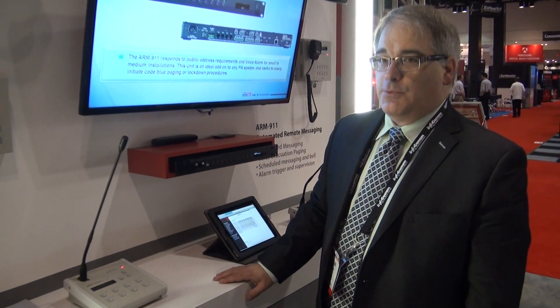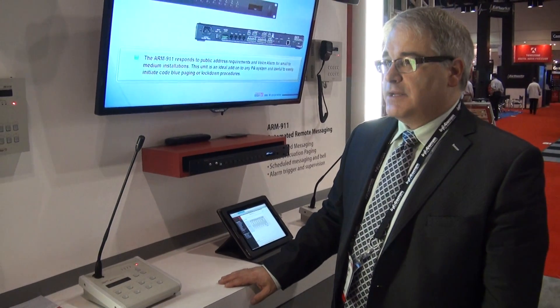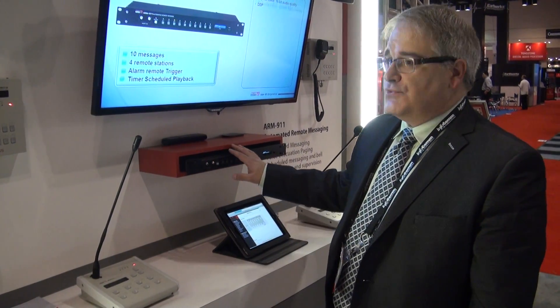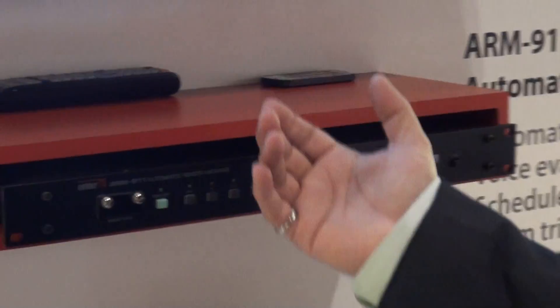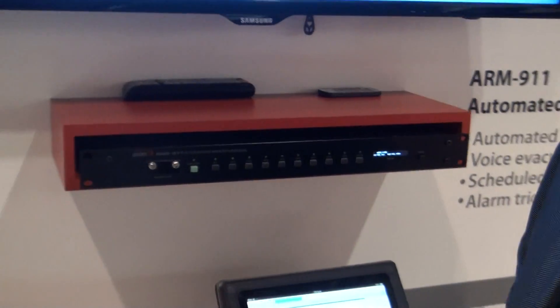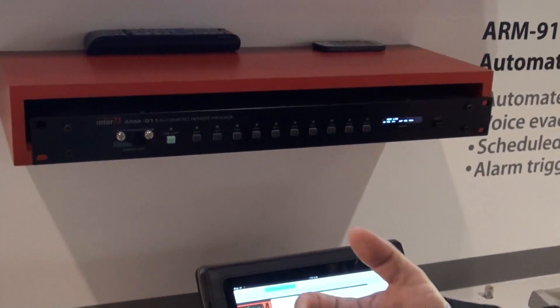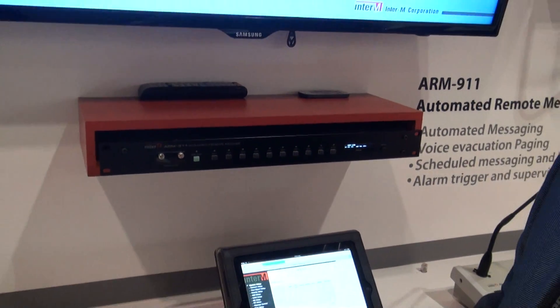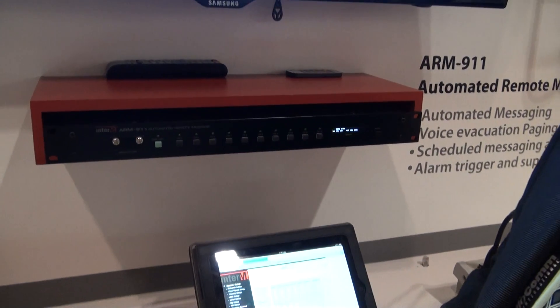And if you need to evacuate the premises as well, you can use this device to do so. The unit also features 10 contact closures — the front 10 buttons are reproduced in the back with optically coupled relays. This allows you to interface the unit with a fire alarm system or any other external triggering device in order to trigger any of the messages as you wish.